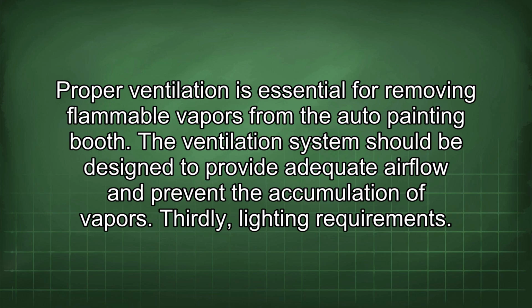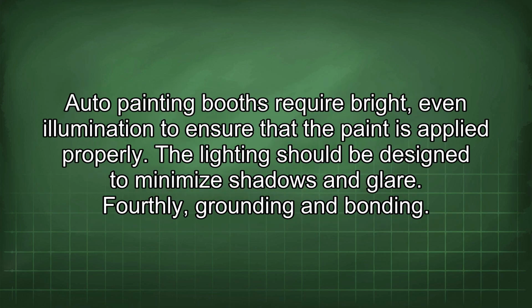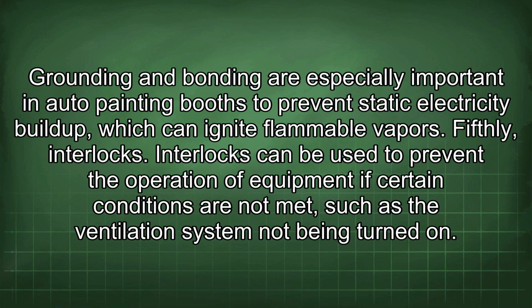Thirdly, lighting requirements. Auto painting booths require bright, even illumination to ensure that the paint is applied properly. The lighting should be designed to minimize shadows and glare. Fourthly, grounding and bonding. Grounding and bonding are especially important in auto painting booths to prevent static electricity buildup, which can ignite flammable vapors. Fifthly, interlocks. Interlocks can be used to prevent the operation of equipment if certain conditions are not met, such as the ventilation system not being turned on.